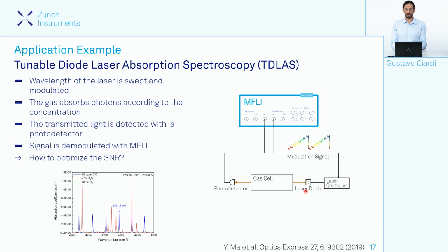When the wavelength of the light matches one of the absorption lines of the species inside our gas cell, the photodetector records a reduction in the light intensity. Now, when the concentration of the gas is ultra low, so there are very few molecules that contribute to the absorption of light, the signal is extremely small and very hard to detect. What is usually done to increase the sensitivity of this technique is to add a small sinusoidal modulation to the driving signal of the laser diode, and this has the effect, as we have seen before, of shifting our signal to the frequency of this modulation, thereby increasing significantly the sensitivity of the measurement.